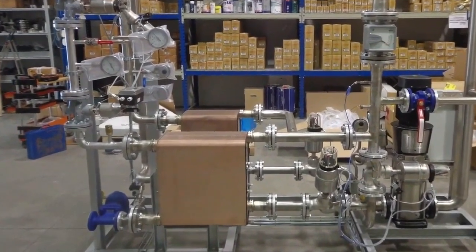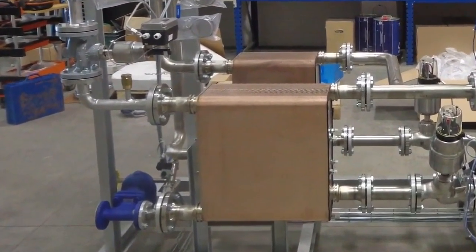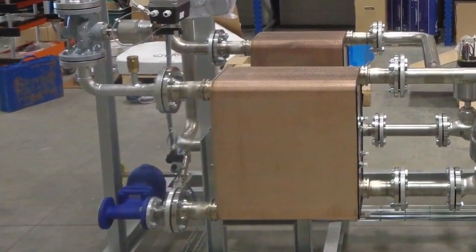The steam must inevitably enter from above so that the condensation can drain downwards and be completely drained from the heat exchanger. Using steam, it's possible to reverse primary and secondary circuit, but not the flow direction in this case. For steam, it must always be top to bottom.